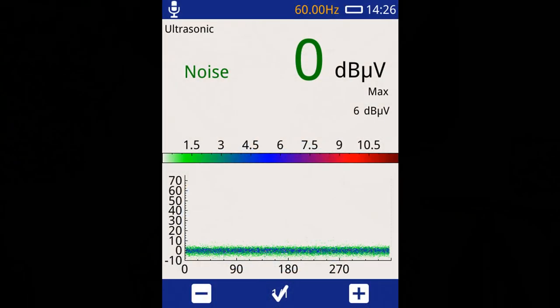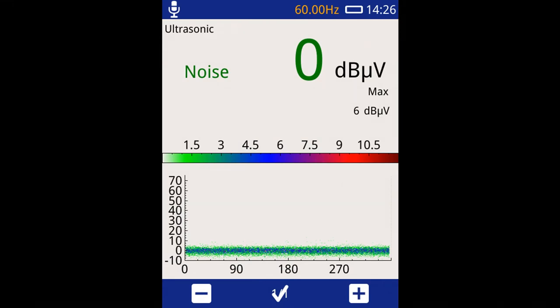If you need to go to manual, that's also there, so you could press manual, and when you press manual the screen will clear and you'll see the phase resolve plot again. On the far left and far right will be a negative sign and a plus sign to lower and raise the value of the frequency, so you can make adjustments incrementally. Then, when you're satisfied, in the middle button there's a little check mark — you press that button to lock it into play. That's how you would set up a manual phase reference point.